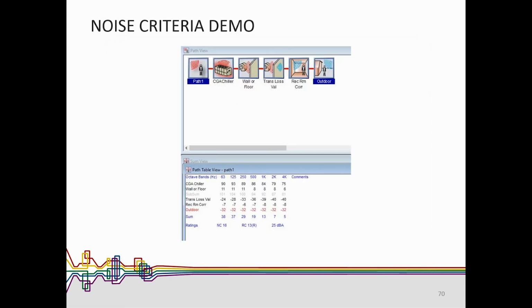So that's the way that works. The other thing you can do is some manufacturers offer this for free. This one you pay for, it comes from a manufacturer down in La Crosse. You have these little blocks you connect with lines, and you can say, in this case I did a chiller because it was easier for me than an air handler. You put a wall in, put the room conditions in, say where you are, and in the end it gives you the answer down below. It says it's an NC 16 inside this particular room. But that's the contribution from a chiller, so that's a little different than normal.